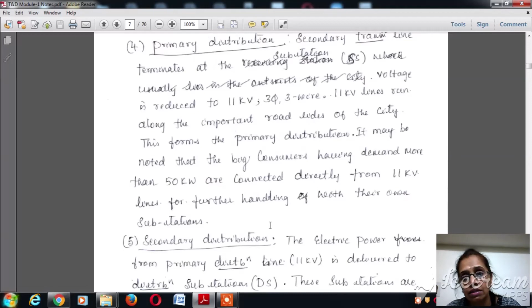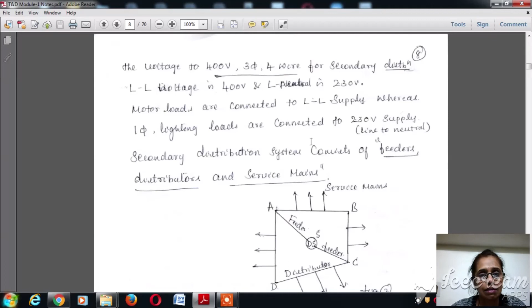Now the secondary distribution: the electric power received from the primary distribution line at 11 kV will be further reduced to 400 volts and then to 230 volts. This substation is called the distribution substation, which is situated inside the city. The voltage levels are 400 volts, three-phase, four-wire for secondary distribution. The line to line voltage of 400 volts is required for the industries, and the line to neutral voltage of 230 volts is required for lighting loads and residential loads. Motor loads and heater loads are industrial loads, and they tap the line to line supply, while the lighting loads tap 230 volts, which is line to neutral, that is a single phase line.